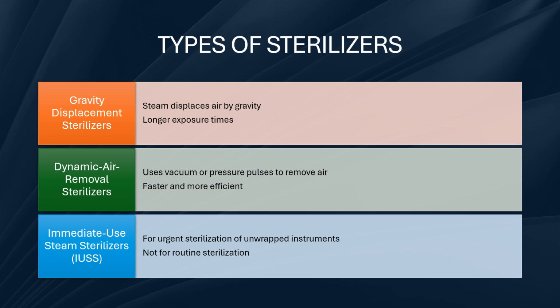The immediate use steam sterilizers, or the IUSS. Back in my day, it was known as the flash sterilizers, but they changed the name about 10 plus years ago. So now it's known as the immediate use steam sterilizers, or the IUSS. This is used only when instruments are needed urgently. They are sterilized unwrapped or semi-wrapped quickly, but are not recommended for routine sterilization due to a higher risk of contamination.